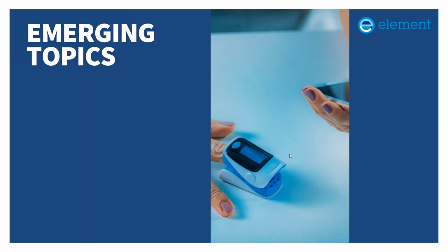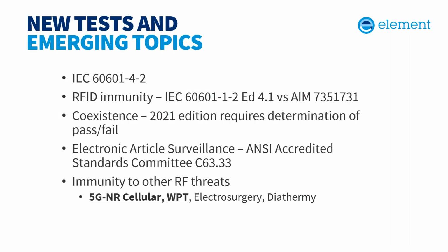So emerging topics: what's new in medical device testing? I previously mentioned the first 3 topics here, but I'm going to just briefly touch on them. The first is 4-2. We're seeing a lot more pushback from the FDA on products that have not been evaluated to 4-2, meaning as medical device manufacturers, you'll want to investigate applying that to your device during testing on the first round instead of having to come back or reevaluate after submitting to the FDA. RFID immunity: I mentioned edition 4.1 is intended to replace the requirement to do AIM testing, but we've heard from people that they've seen susceptibility to AIM, but not to edition 4.1. So they're similar levels and signals, but the modulation is different and different results are being reported.